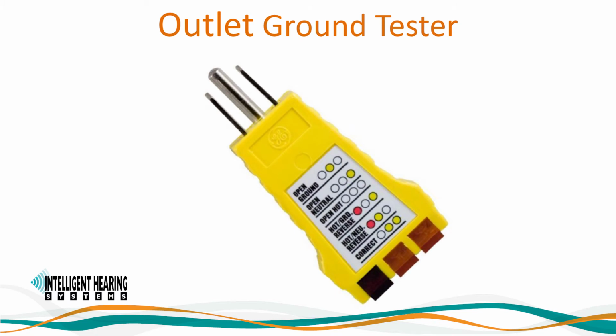Grounding the IHS device is the most important component to ensuring good quality recordings during testing. I emphasize that the system, the computer, 3-prong grounded power supply, and any peripherals such as the printer need to be connected to the same ground. You can check the grounding on room power outlets using a ground check plug as shown here. If the device is set up on a metal cart, then you will require the use of an isolation transformer and the cart must be grounded to the isolation transformer.